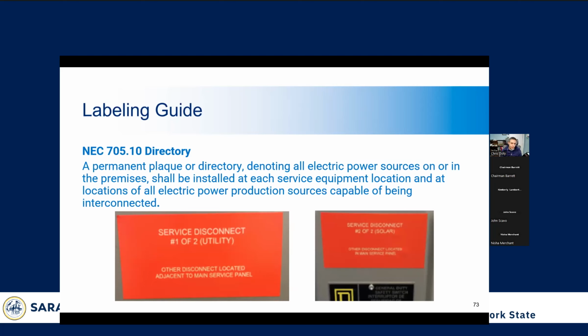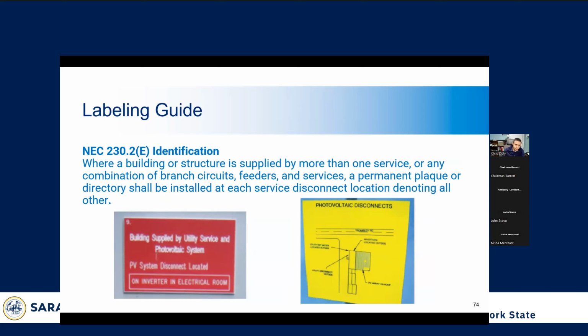Here we have the service disconnects that are labeled, and they have to be labeled with permanent plaques. You can see here they are, and they also give information on where the other disconnect is. So with a solar PV system, typically you'll have two disconnects. Of course, the service disconnect for the utility, and then the solar disconnect, which is typically the backfeed breaker. So you want to make sure that if someone turns off one, they know that there's another one, so that when they're working in that panel, it is electrically safe.